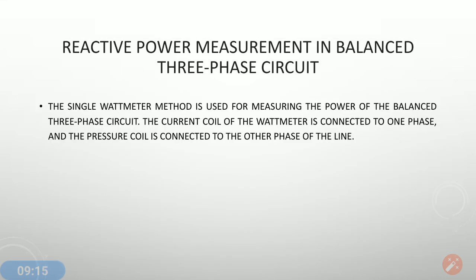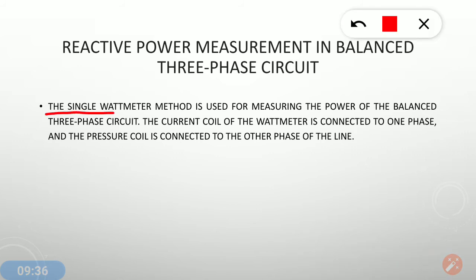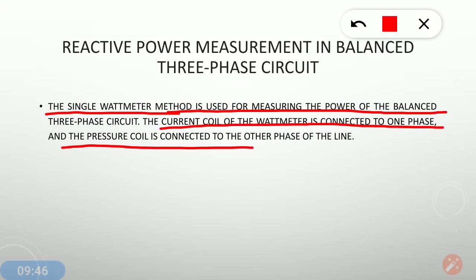Now, the reactive power measurement in a balanced three-phase circuit. For a balanced three-phase circuit, a single wattmeter method is used for measurement of reactive power. The current coil is connected to one phase and the pressure coil is connected to the other two phases of the line.